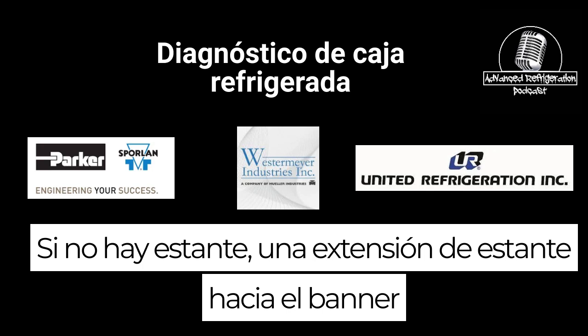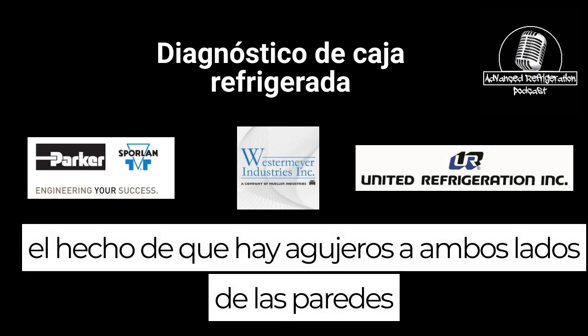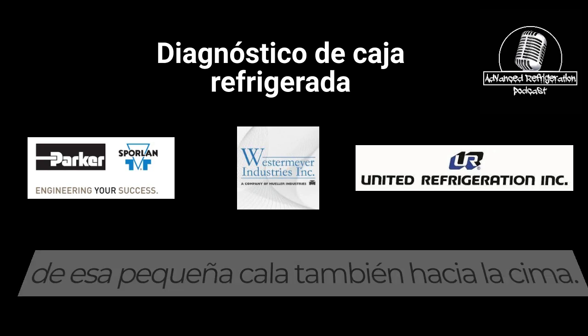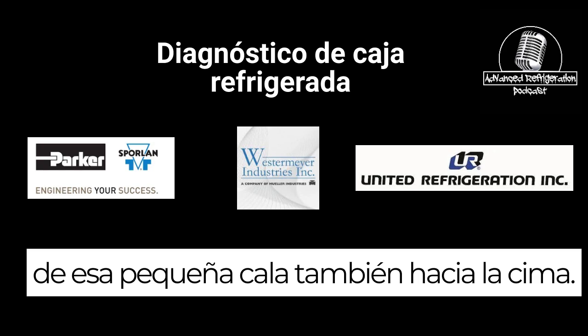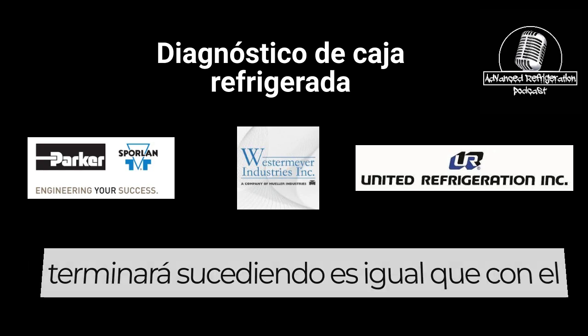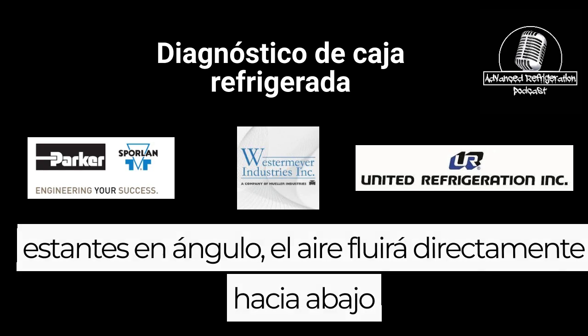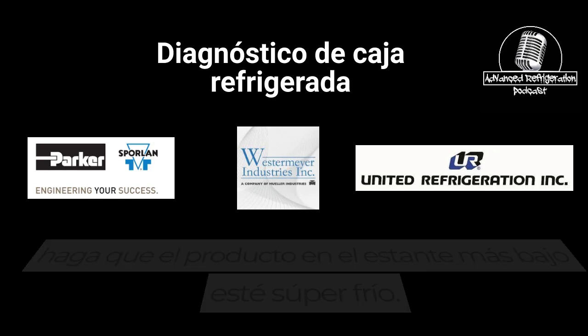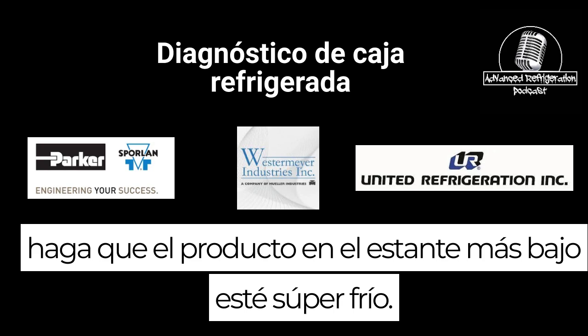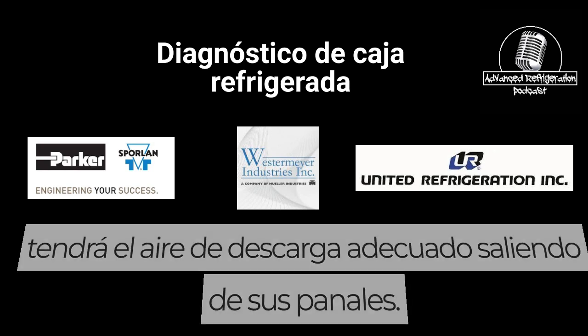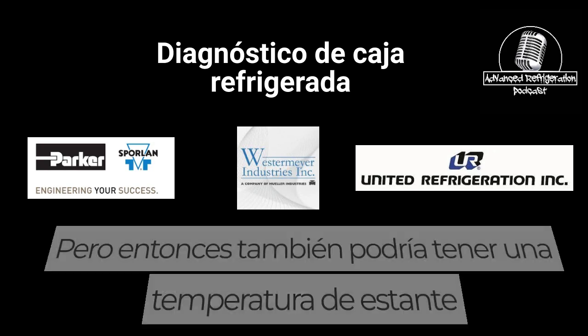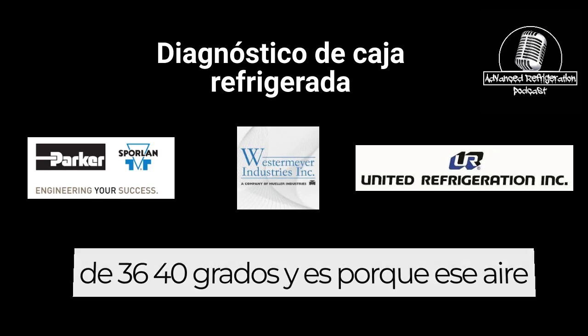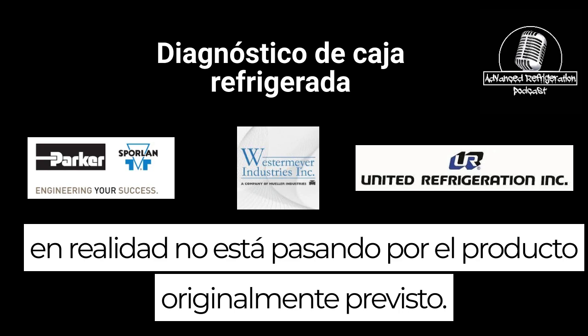If there is not a shelf extender in toward the back, and there are holes on either side of the walls of that little alcove towards the top, if the shelf extenders are not in there, what'll end up happening is, just like with the angled shelves, the air will just flow directly down to the lowest part of the case and basically make the product on the lowest shelf super cold. And then on all the rest of the shelves, you will have the proper discharge air coming out of your honeycombs, but you also might have a shelf temperature of 36, 40 degrees. And it's because that air isn't actually going across the product as originally intended.